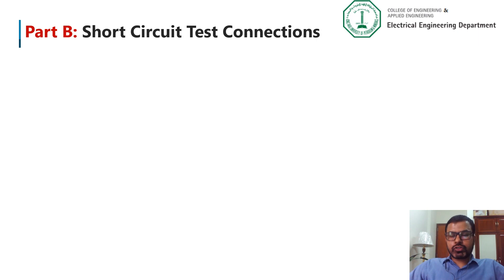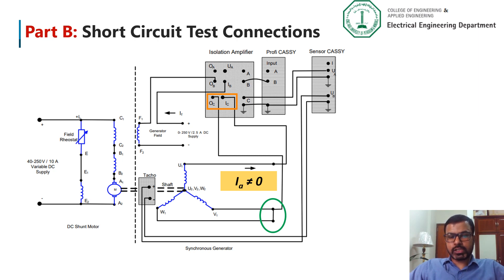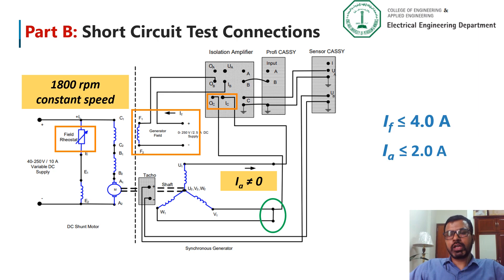In part B, we will study the short circuit characteristics of the synchronous generator. As you can see from the circuit diagram, terminals V1 and W1 of the synchronous generator are shorted, whereas the other two terminals are connected to an ammeter. So the armature current will not be zero as in the open circuit test. For the short circuit test, we have to keep three things in mind: the field excitation should not exceed 4 amperes, the armature current should not exceed 2 amperes, and the motor speed should be kept constant at 1800 RPM.